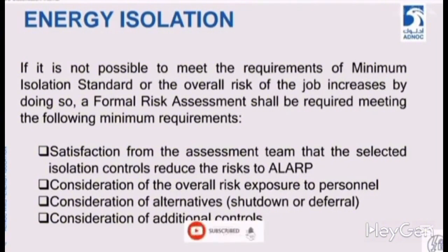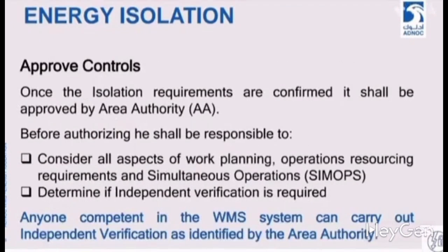These are the points that, under any condition, if we are unable to achieve the minimum standard of isolation, passive isolation or double isolation, we must conduct a formal risk assessment. Within this, we must necessarily consider and implement these four major points. It is necessary to implement them. Approve control of energy isolation. The isolation requirements are confirmed and should be approved.